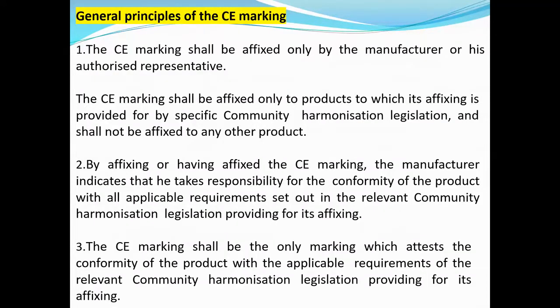The CE marking shall be affixed only by the manufacturer or his authorized representative. The CE marking shall be affixed only to products to which its affixing is provided by specific community harmonization legislation and shall not be affixed to any other product. As I told you, if there are several components, it should be affixed only to the product to which its affixing is provided for by the specific community harmonization legislation.